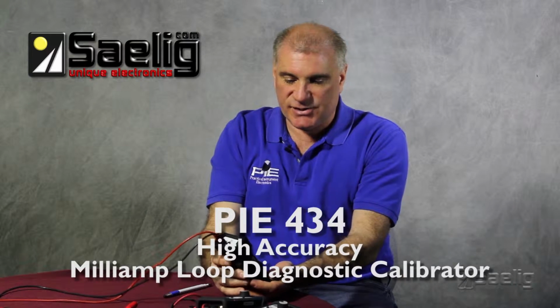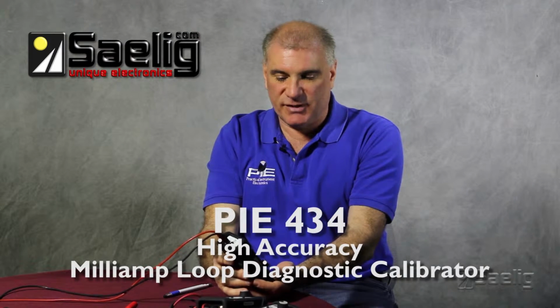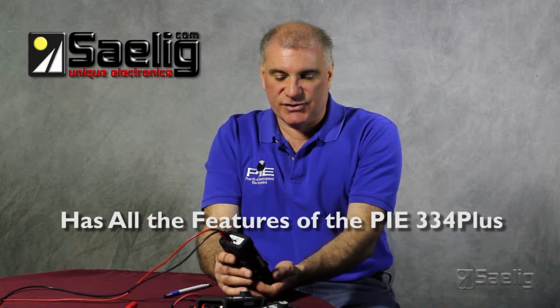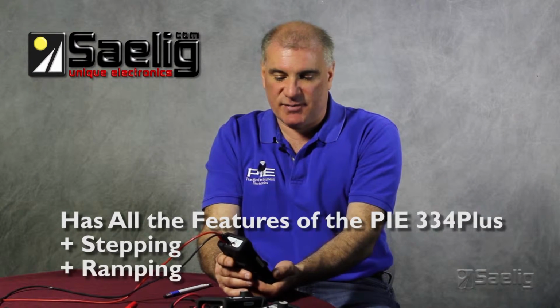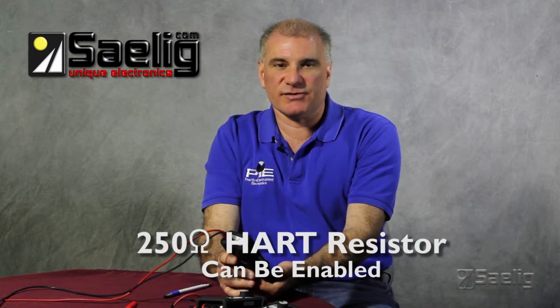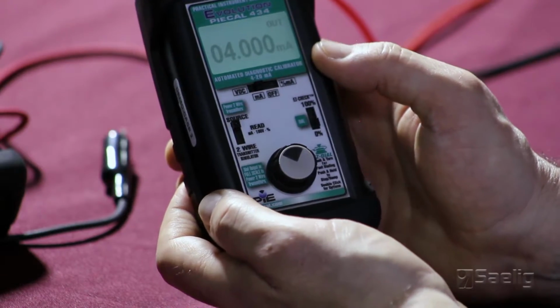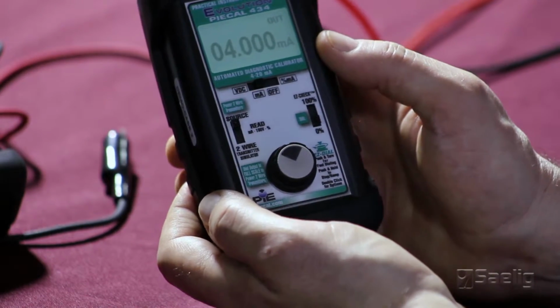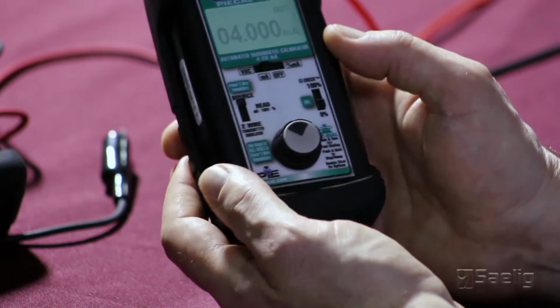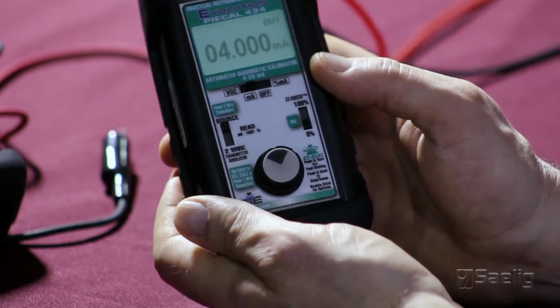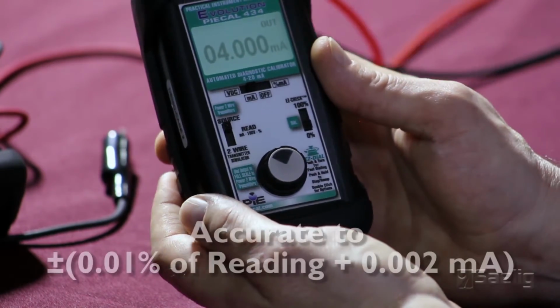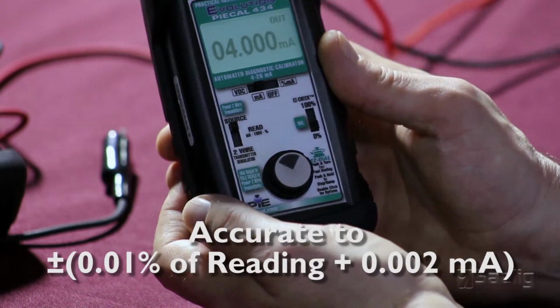Our PIE 434 has the same features as the 334 Plus, but also has other automated functions such as stepping and ramping. It also has a 250 ohm HART resistor which can be enabled, along with auto on and off and backlight that can be turned on and off. The 434 is also a high accuracy calibrator, up to 0.01% of the reading.